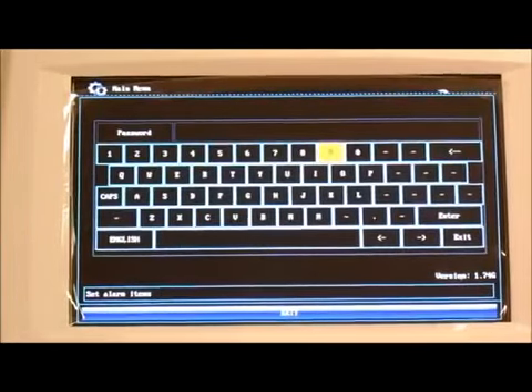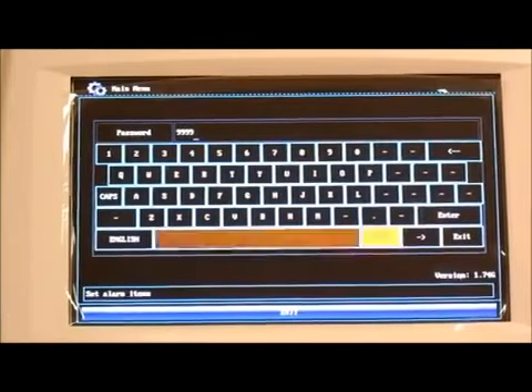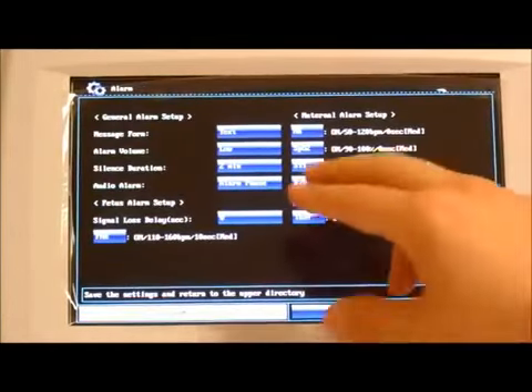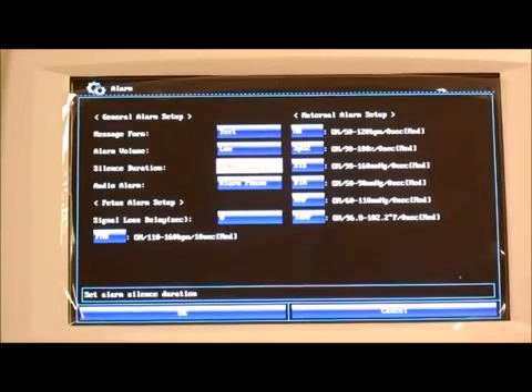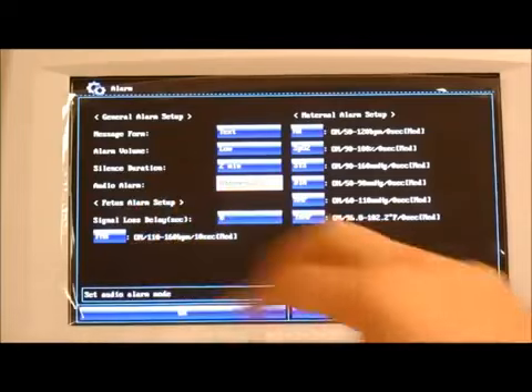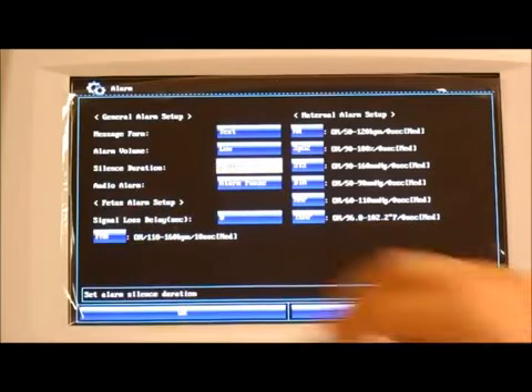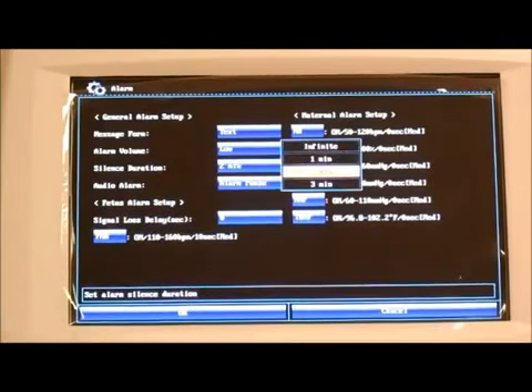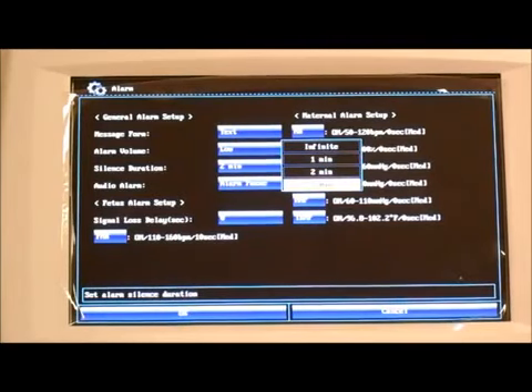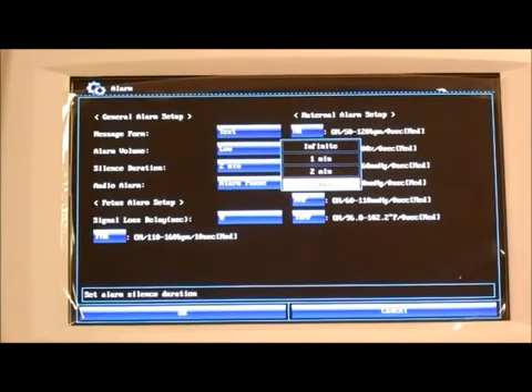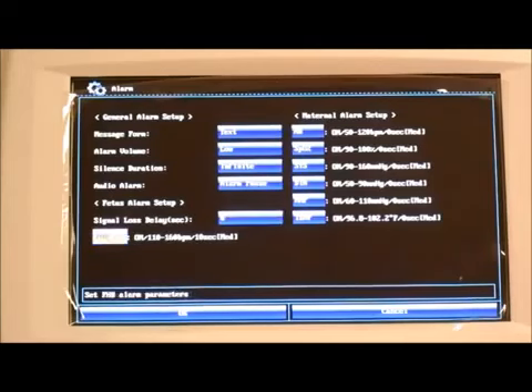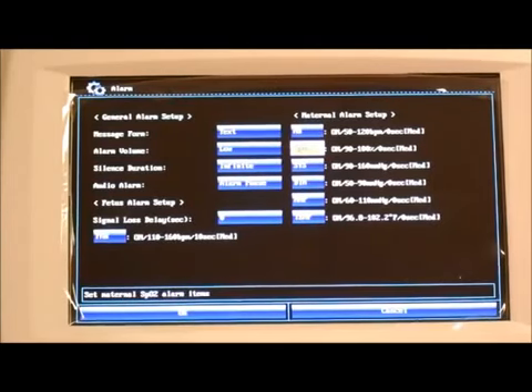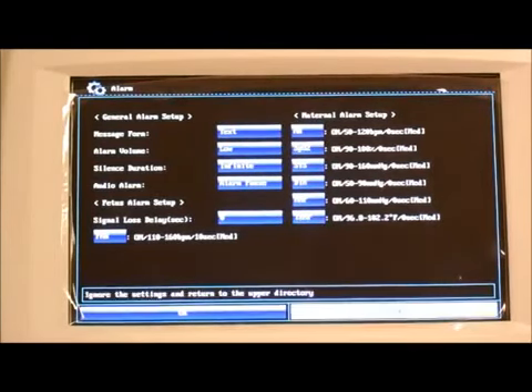Your alarm, again, here we can adjust your ranges. And the other setting of interest that I wanted to point out, it's the alarm pause setting or silence duration. If we set it to 1 minute, 2 or 3 minutes, it'll only be muted for those specific reference points. If you set it to infinite, it'll be an infinite or a long-term mute. Okay, so alarm, we can adjust all your alarm ranges for all your parameters.